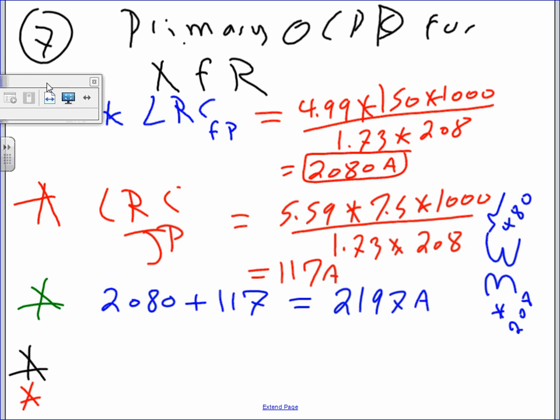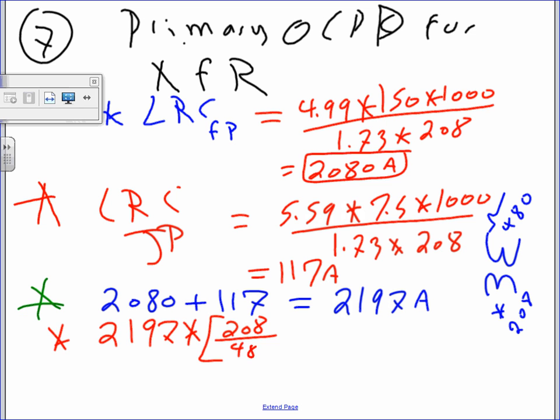So the last thing you need to do is take the number that I came up with, which is 2197, multiplied by the voltage ratio. What's the voltage ratio? 208 divided by 480. And that will transfer the amps from this side of the transformer to the other side. If you do that, that will give you 952 amps.